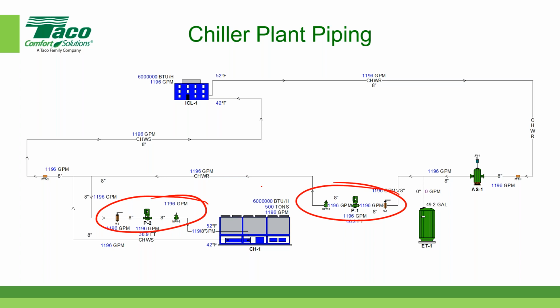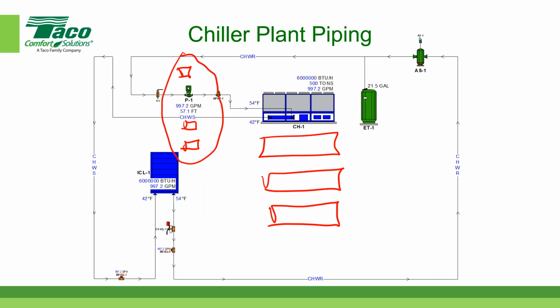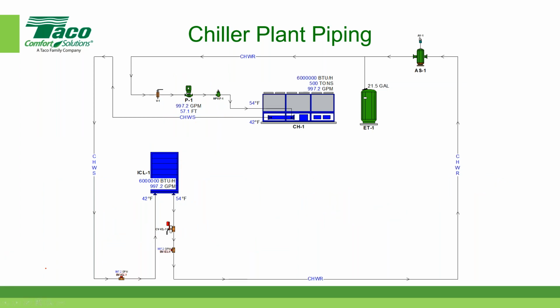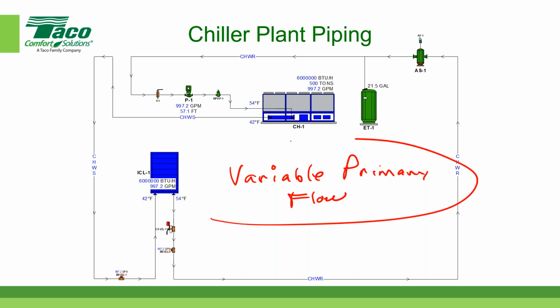So what we're seeing in terms of system configurations is that more and more new chiller plant designs are going with a variable primary flow. And designed properly, you can reduce the amount of energy consumed. By using multiple chillers and multiple pumps, you can get that fraction quite low.